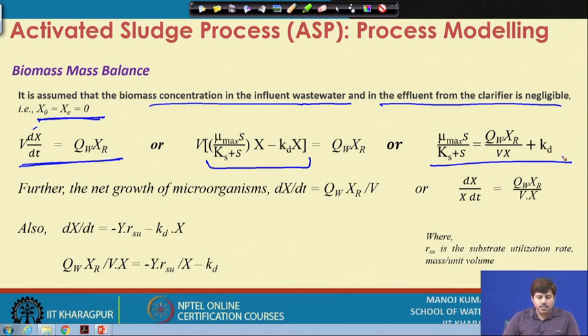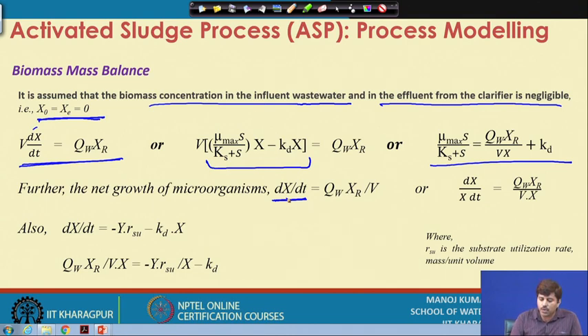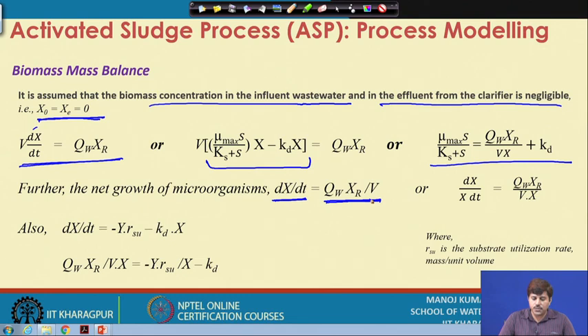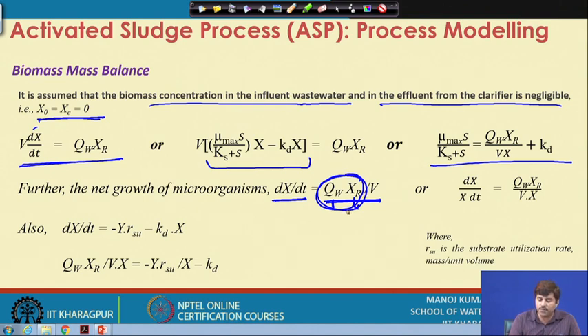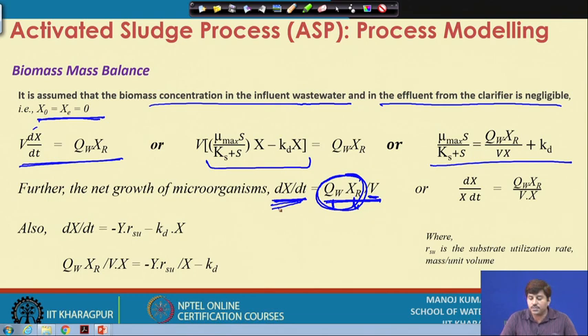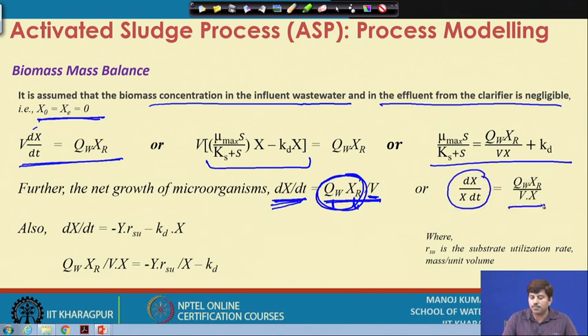At steady state, the net amount of biomass growing in the system must equal the net amount of biomass being wasted. So Qw·Xr represents the total biomass being wasted per unit volume of the aeration tank, and this equals the rate of net biomass growth. Rearranging, we get dX/dt divided by X equals Qw·Xr / (V·X).